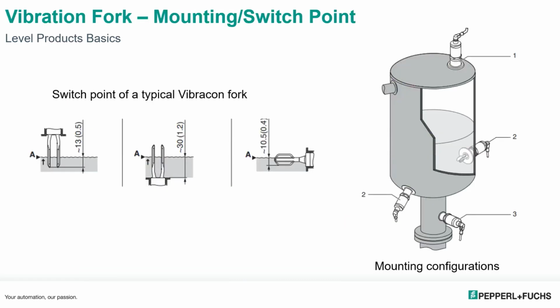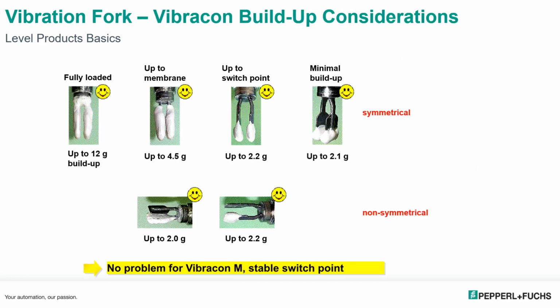Now this shows you the switching points of the forks, whether it's mounted from the top, bottom, or on the side. The one thing to note about the Vibracons is that you will have two forks coming out, and they vibrate. They could have a buildup on them. These pictures give an example of the buildup that's possible on these Vibracons while they still work. As you can see from the top, it's pretty symmetrical, but even if the buildup is not symmetrical, it can still work properly.